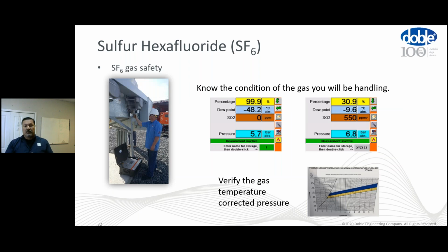Know the condition of the gas you'll be handling. This is really important in preparing yourself. You want to know that you're dealing with clean gas or you're dealing with contaminated gas. So field testing of the gas before you handle that gas, before you connect to it, is really important. What kind of pre-filters do I need? Do I have a low purity, which means I may have air or other vapor contaminants in there, which means I need more storage space? So really important. Verifying the temperature corrected pressure is very important for a couple of things. One, it's going to tell you if this thing is leaking. Two, is it overfilled? Is it underfilled? Do I need to prepare myself to recover that final amount with air contamination? So again, knowing what the correct temperature corrected pressure is and the condition of the gas is part of your planning and part of preparing for the recovery.